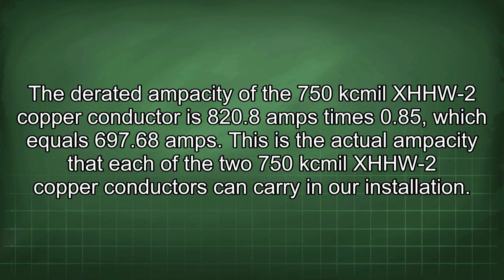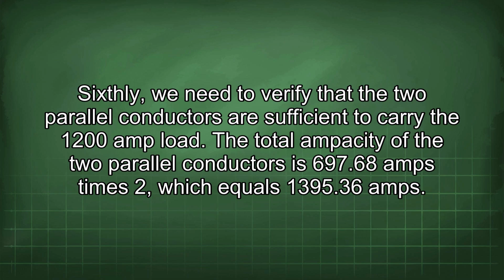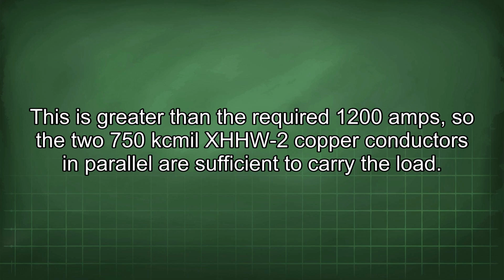The derated ampacity of the 750 kcmil XHHW-2 copper conductor is 820.8 amps times 0.85, which equals 697.68 amps. This is the actual ampacity that each of the two 750 kcmil XHHW-2 copper conductors can carry in our installation. Sixthly, we need to verify that the two parallel conductors are sufficient to carry the 1200 amp load. The total ampacity of the two parallel conductors is 697.68 amps times 2, which equals 1395.36 amps. This is greater than the required 1200 amps, so the two 750 kcmil XHHW-2 copper conductors in parallel are sufficient to carry the load.